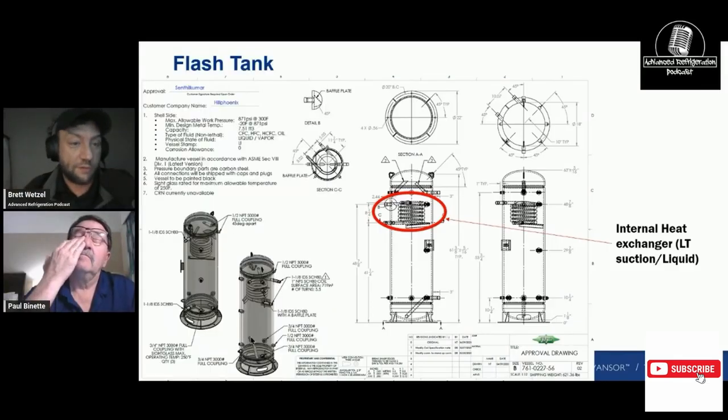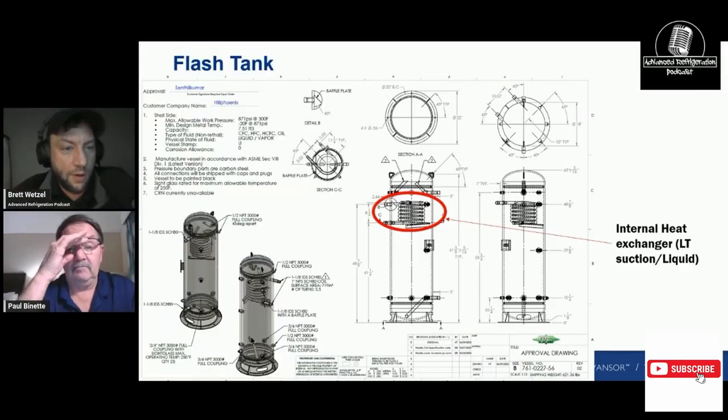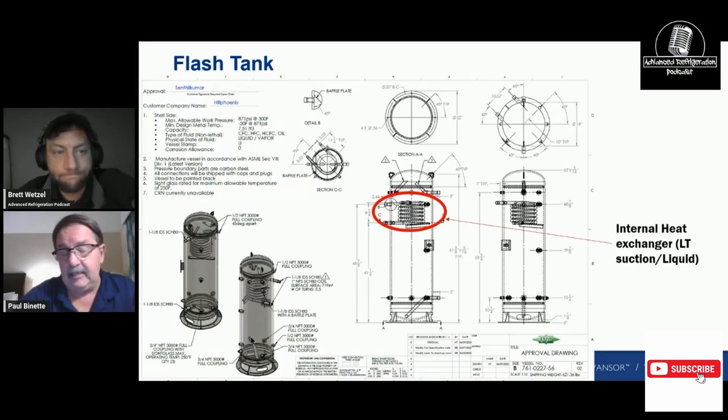The oil is a little bit warmer on the compressor belly — around minus 20. These oils also have a lower limit temperature somewhere in the 50-degree range where we don't want the oil to get colder than that in our reservoir. That's why you have crankcase heaters on for about 24 hours before you actually roll the rack on.